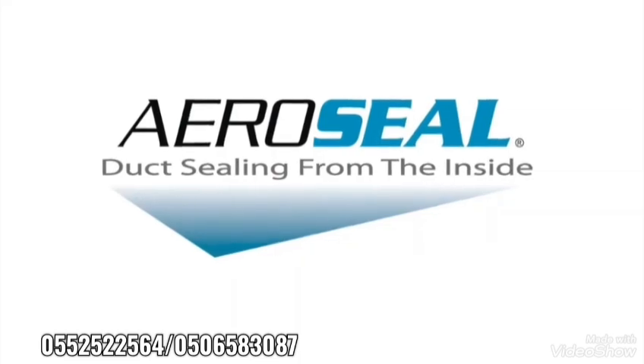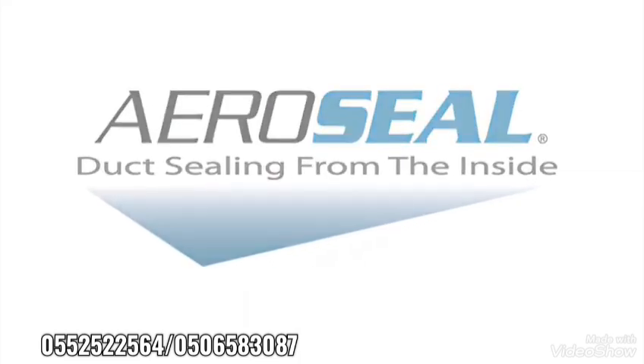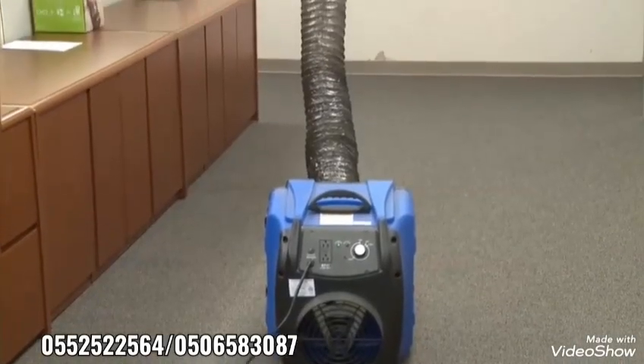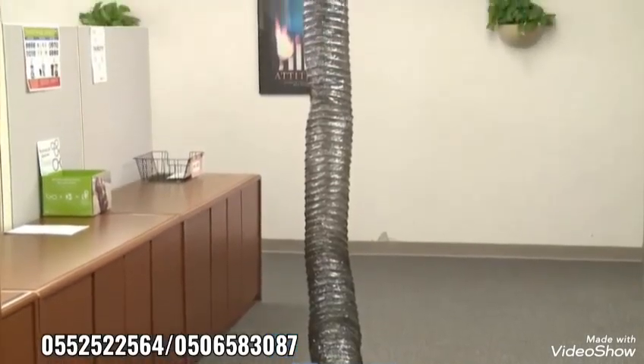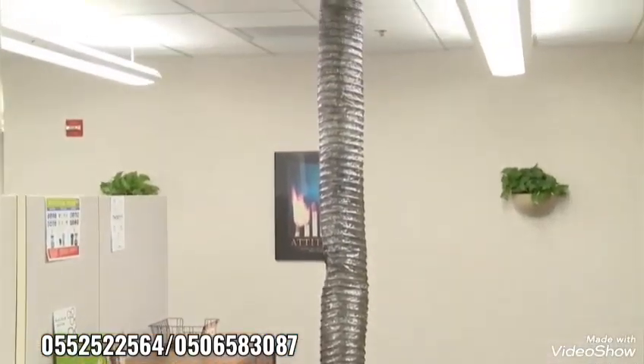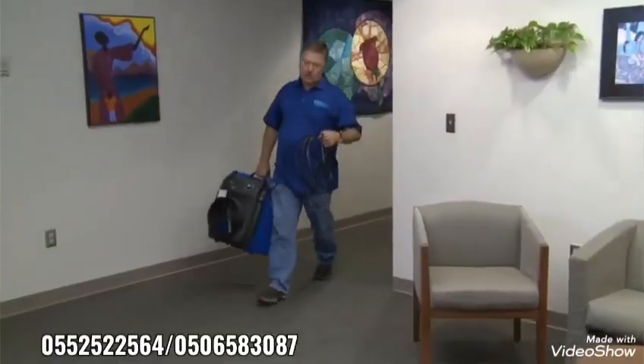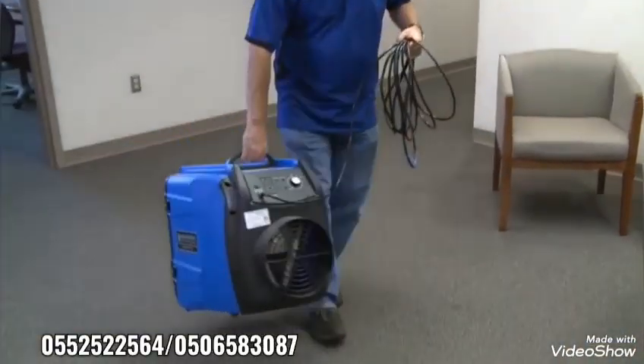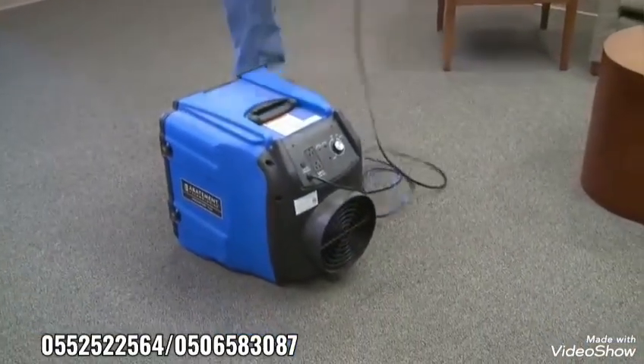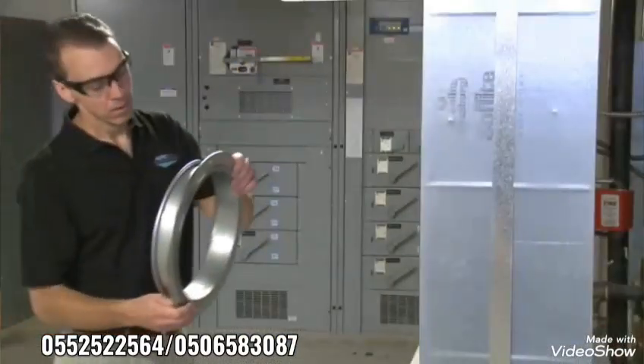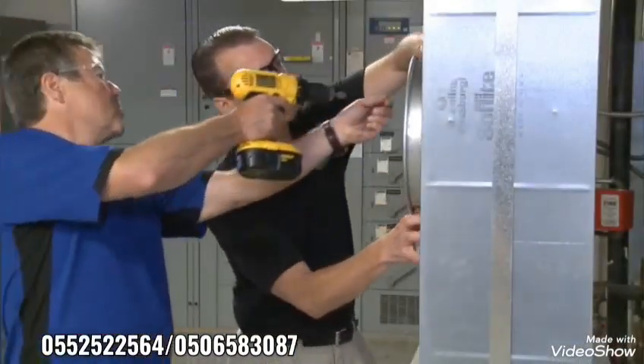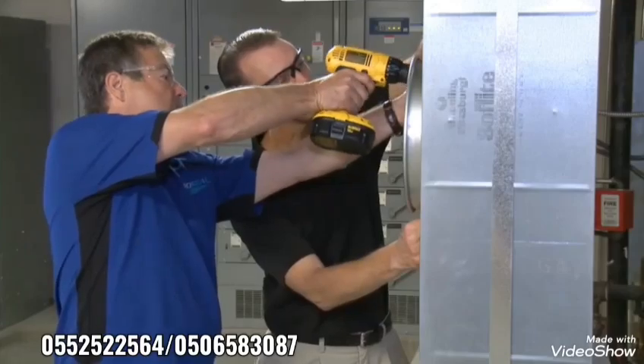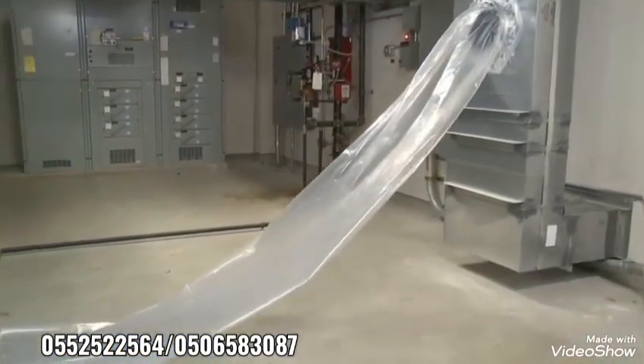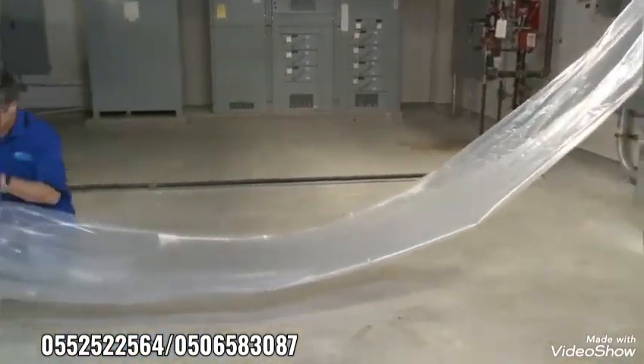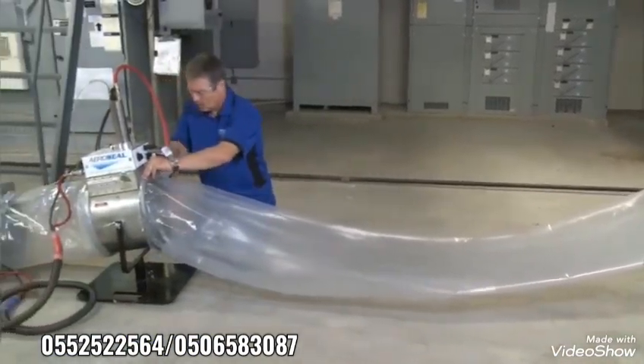Some sealant particles will escape through the holes in the ductwork during sealing. AeroSeal utilizes negative air machines to depressurize sealing cavities and plenums and capture the sealant. Scrubber fans also ensure that any overspray entering occupied spaces is captured. To begin, a temporary collar is attached to an access hole in the ductwork. The AeroSeal injection machine is assembled and connected to the duct system using a long, flexible plastic tube.